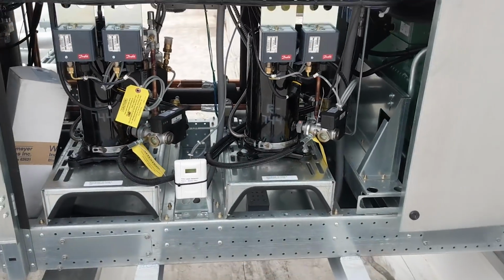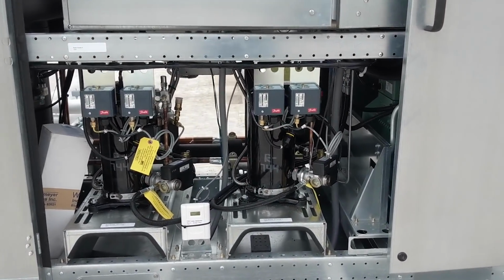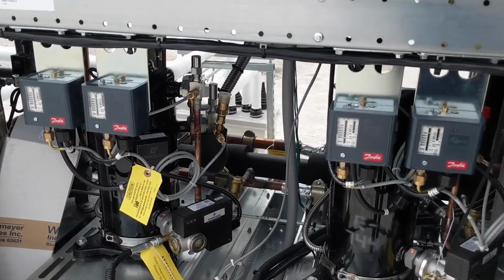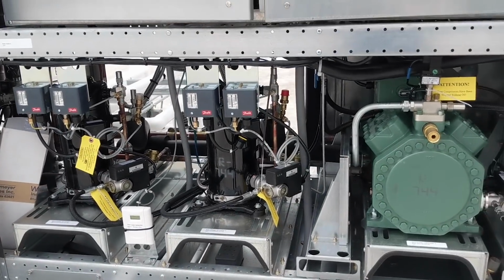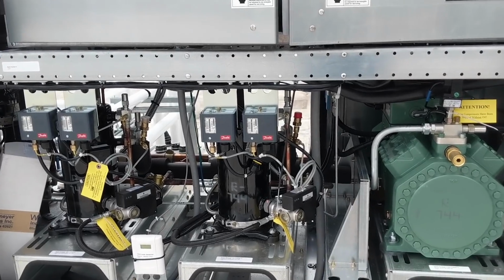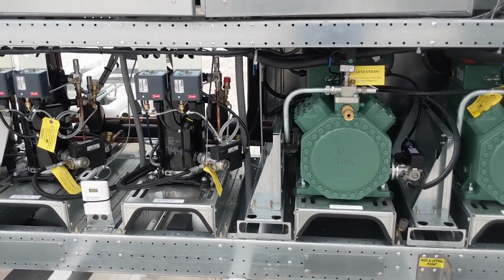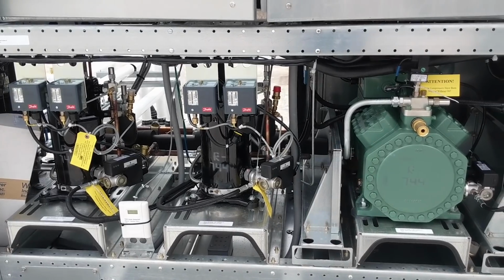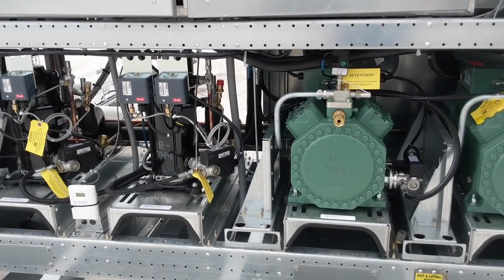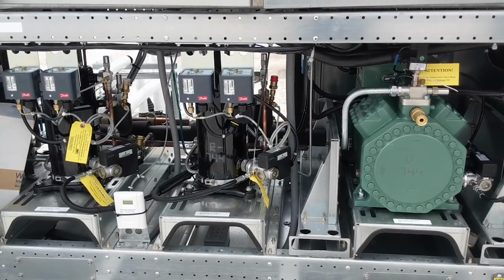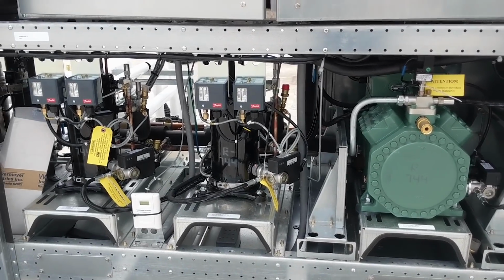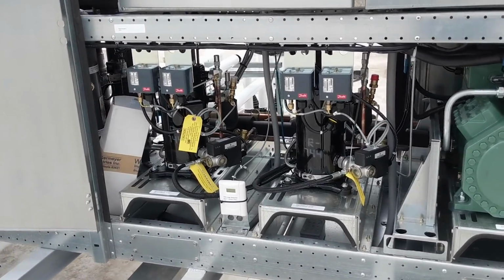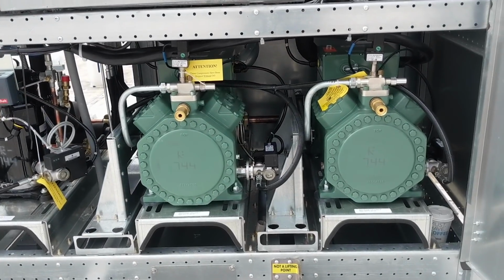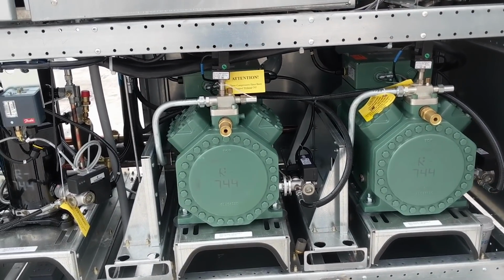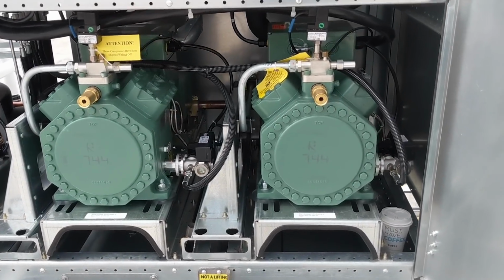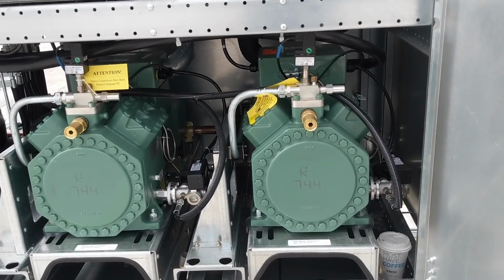So what we're actually doing, this is a 2-stage rack. We're taking the discharge gas of the scroll compressors and we're discharging into the medium temp suction group to reduce the compression ratio, or else we would be going from 200 pounds to 1,200 pounds to 1,600 pounds, depending on the outdoor ambient. That would be a huge compression ratio and a huge efficiency loss. So we are instead going into the medium temp compressors. Why they're so much larger, they have so much more of a load on it.